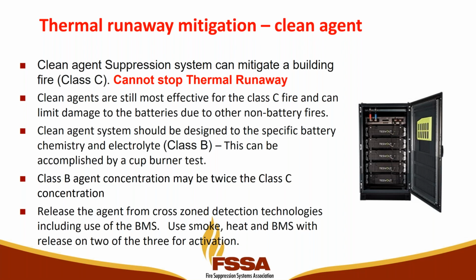Keep in mind, clean agents are very good at Class C fire, and they would do a very good job on that. So for anything inside the cabinet or building that is a non-battery fire, they're going to put that out and save you batteries. But you need to test for an electrolyte fire through a cup burner test, and I would say most of the manufacturers have done some good history on that to tell you what concentrations are needed. But you're looking at almost twice the concentration of agent going from Class C to Class B.